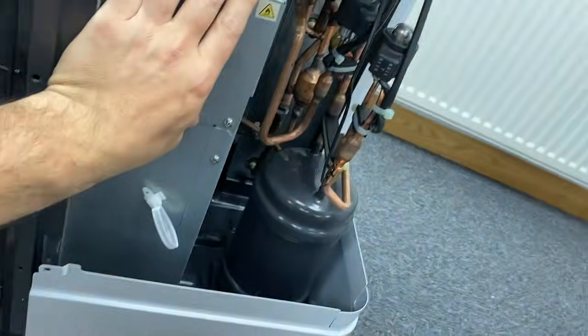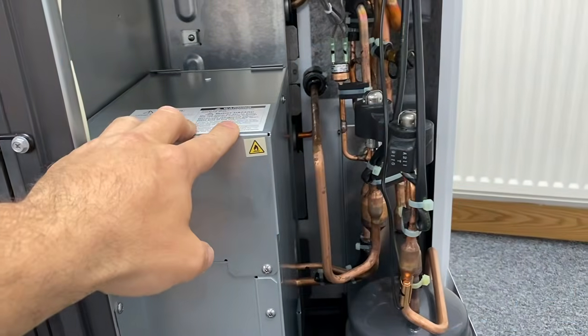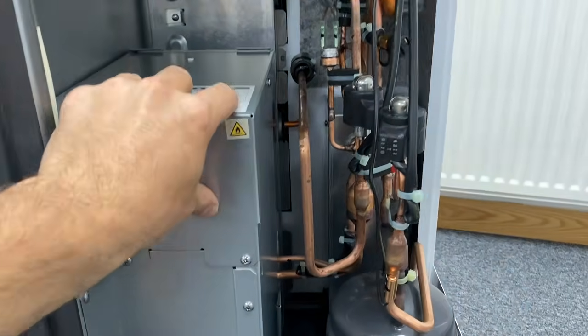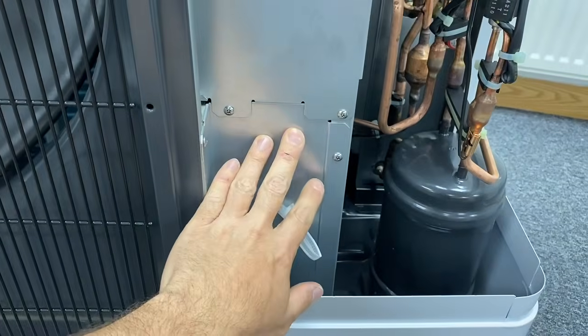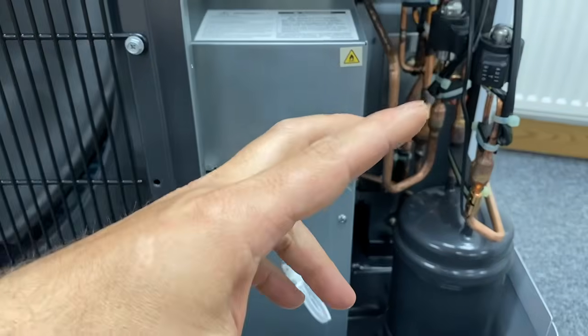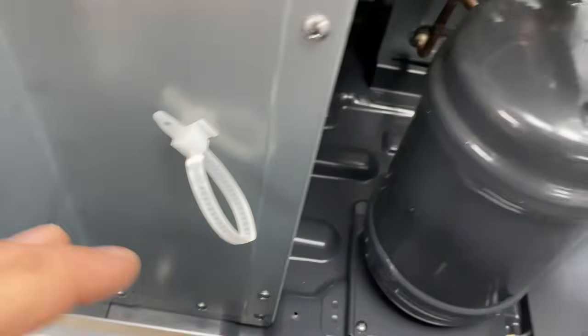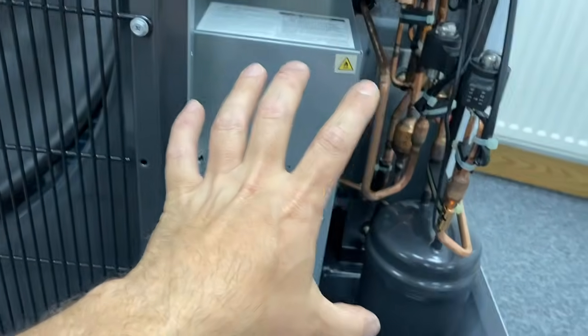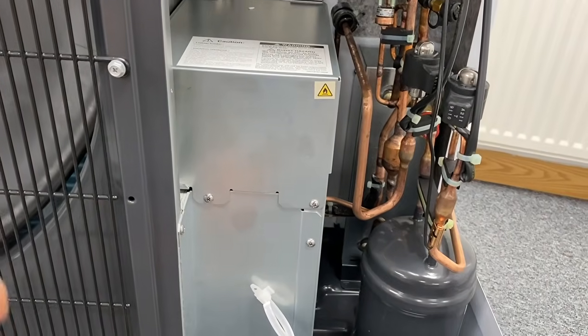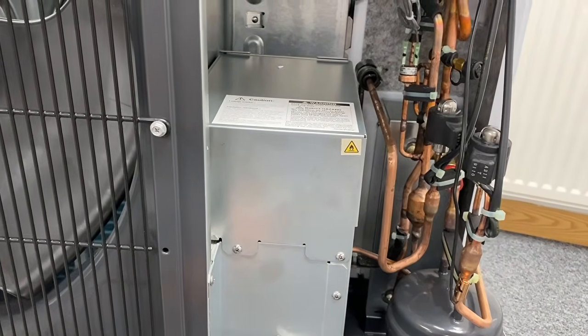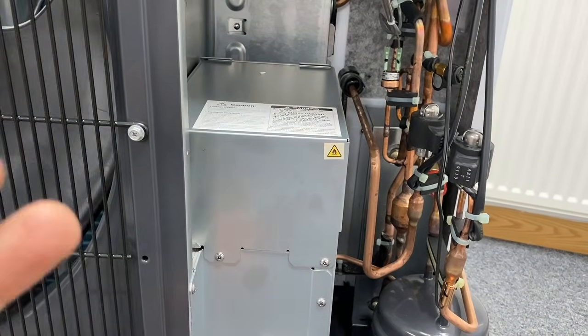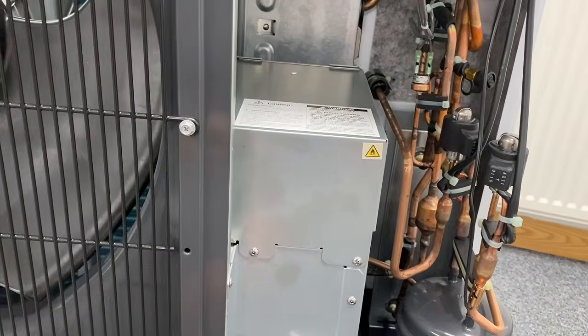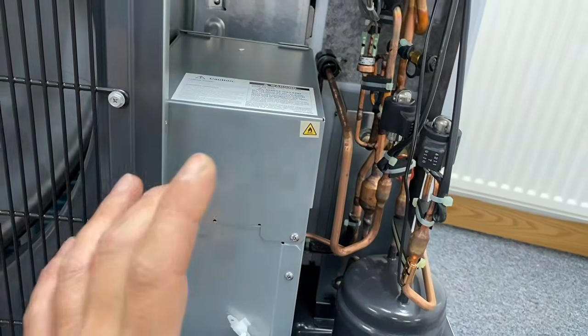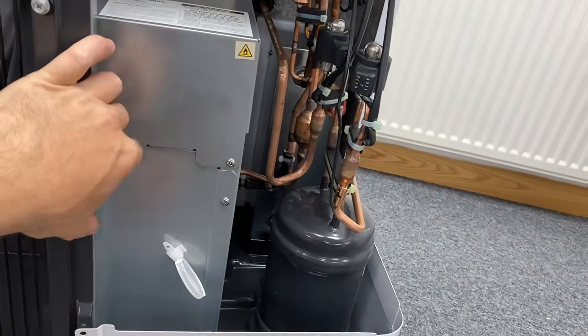Now, in here, on the 11.2s, this is an 8.5, so it's not really going to count. But inside of here, around the compressor, you have to take this packaging off, because inside there are the travel safety bits, which would be polystyrene stuff to stop anything moving about too much, and it's bolted down and stuff. So you read the instructions, make sure that you do remove the packaging that's inside this part here, because if you don't, when that heat pump is running, it will be whistling and blowing, and there'll be a lot of noise coming from it. And often you'll be like, I thought this system was meant to be quiet. If you find that it's noisy and you've got an 11.2, there is a very good chance that the travel packaging on the inside hasn't been removed.